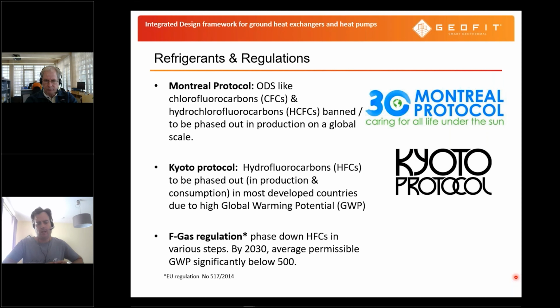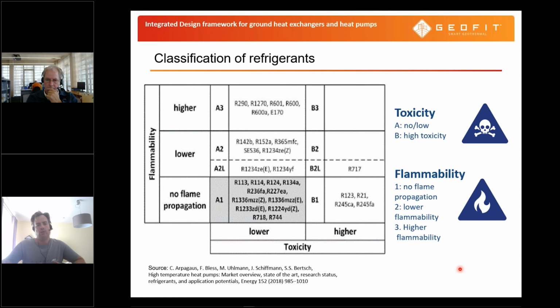So the component manufacturers and also the refrigerant manufacturers have to cope with such regulations in the same way as this phase down. There are of course alternatives, but it's not really an alternative: natural refrigerants are of course getting a little more into focus because they have really low global warming potential. This brings me to the classification of refrigerants.